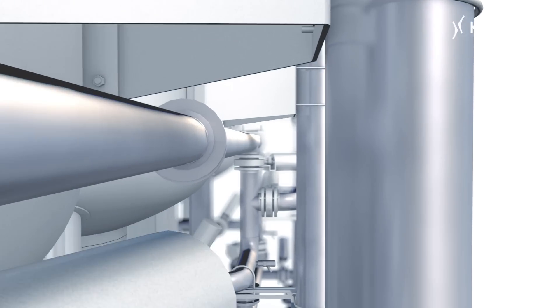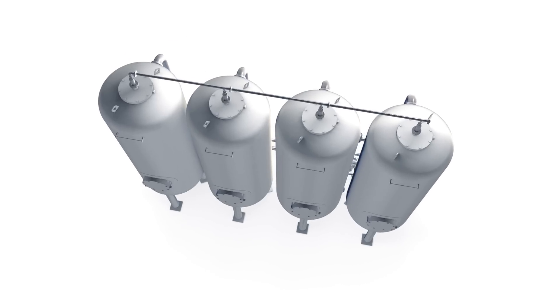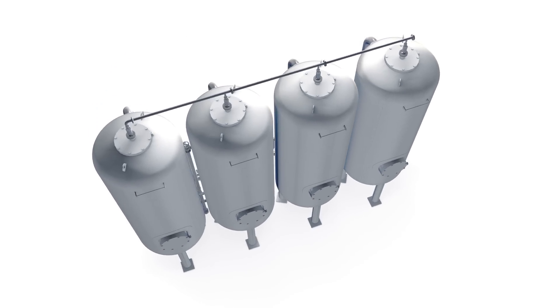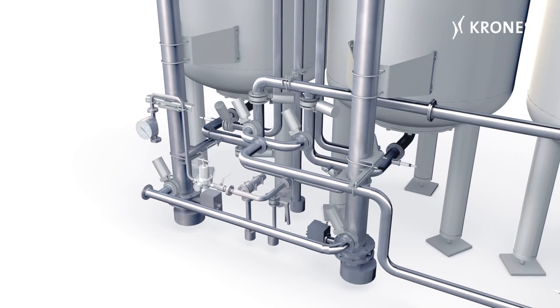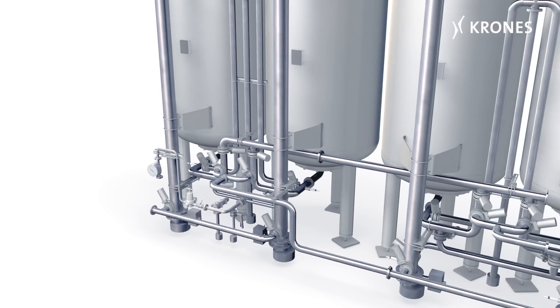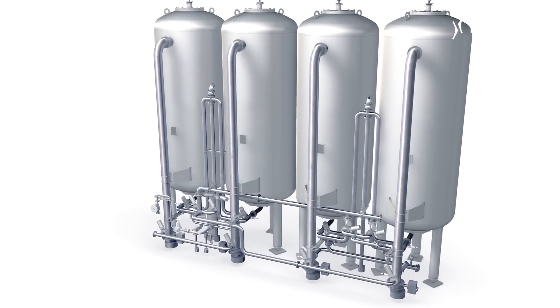It's also possible to remove iron or manganese from the mains water in the traditional manner. The different tanks contain, depending on the initial loading of the mains water involved, different filtering aids such as special granulate, gravel or activated carbon. These filtering aids are in layers, each of them exhibiting a different density.